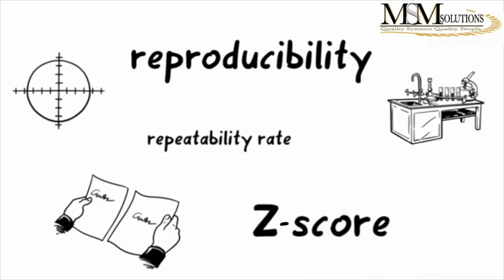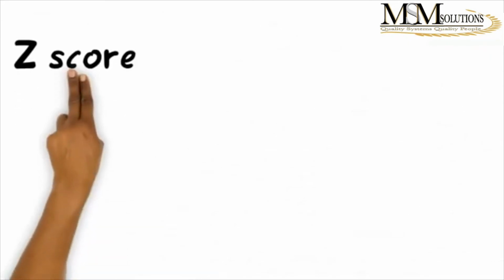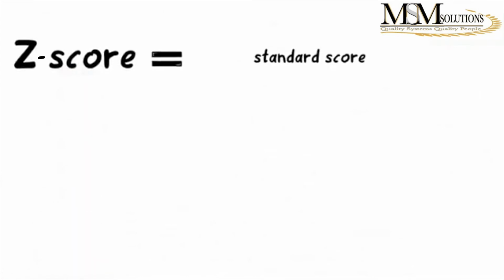When you look at your PT round robin results, you'll see that they've calculated and compared your number to Z-score. So what is a Z-score? A Z-score is also called a standard score. It gives you an idea of how far you are from the mean for a set of data points. More technically speaking, it means how many standard deviations below or above the population mean your raw score is.